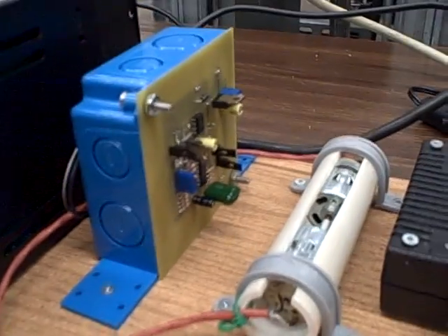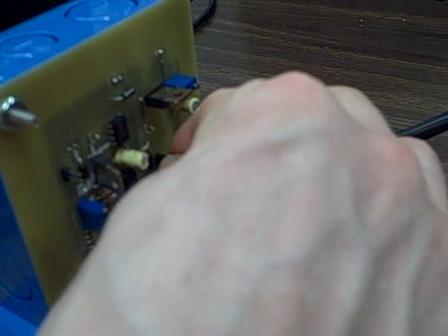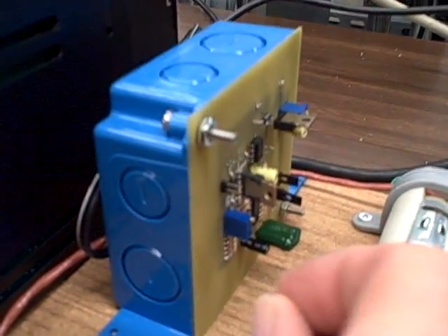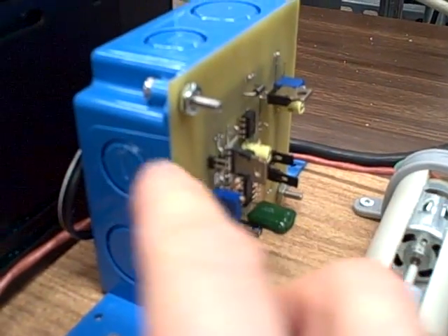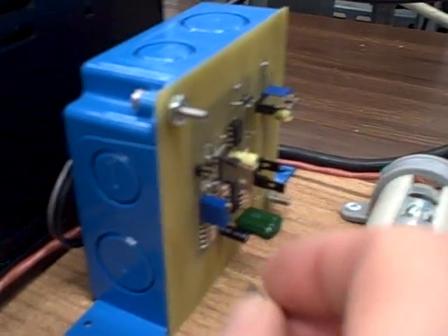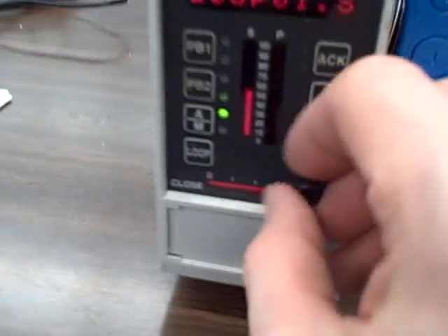I can, for example, go to the variable speed drive. I can pull out the load jumper right here to shut off power to the motor. I can move another jumper from direct action to reverse. Right there, that's the direct reverse jumper. So now when I apply power back to the motor, the variable speed motor drive will act backwards. Now a higher milliamp signal will cause the motor to go slower. Watch what happens. Now here we go.